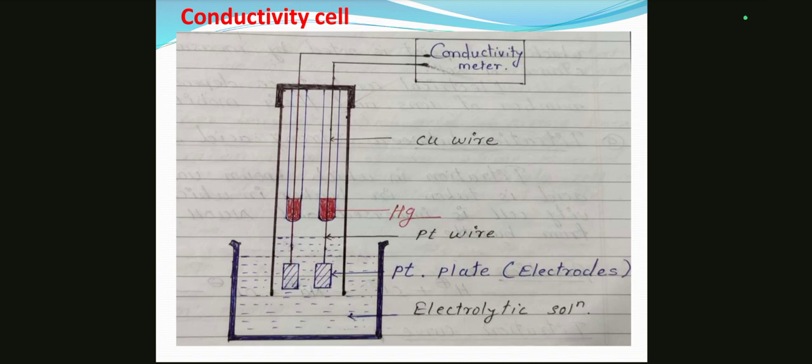That mercury is taken in small glass tubes. From the bottom, 2 platinum wires are inserted in the 2 glass tubes, and those 2 platinum wires are connected to platinum plates. The platinum plates are dipped into the electrolytic solution for measuring the conductance of the solution. The conductivity meter will give you the value of conductance.